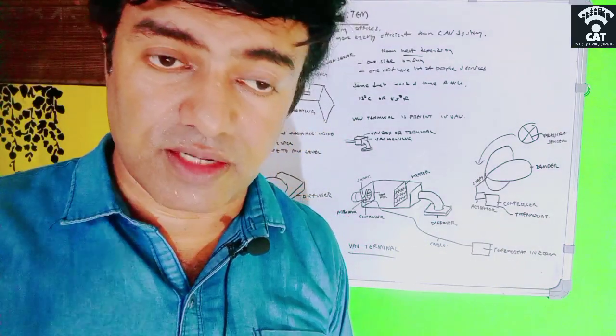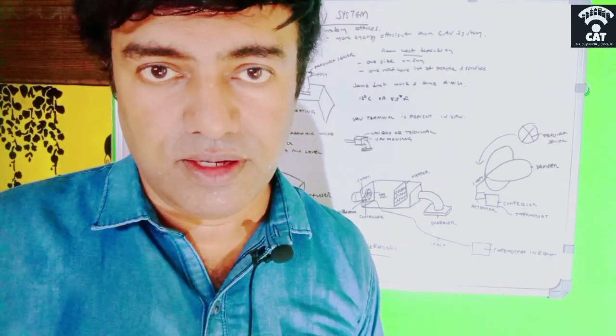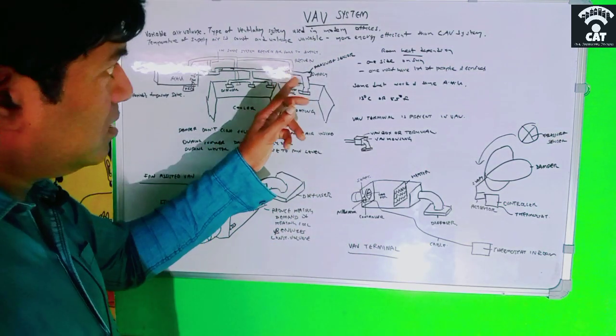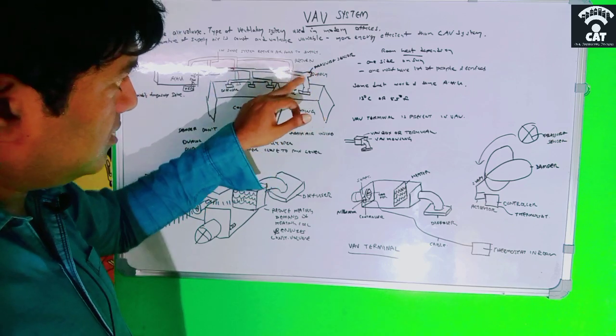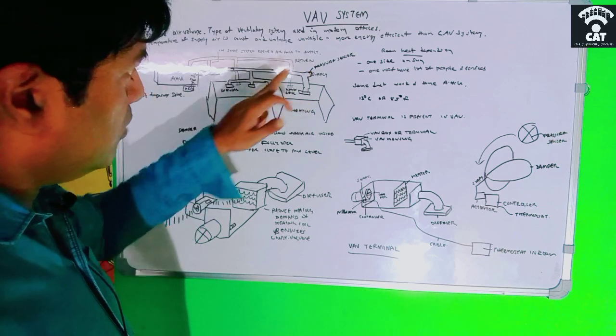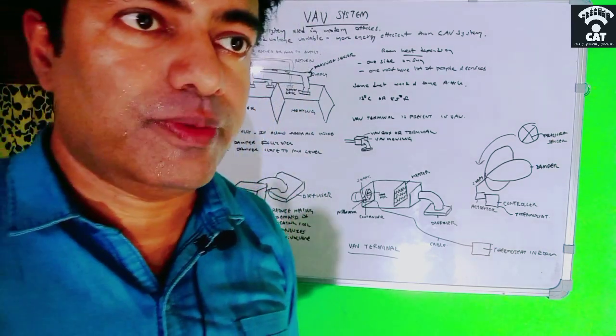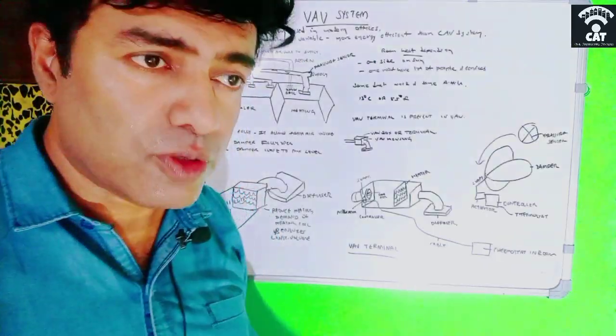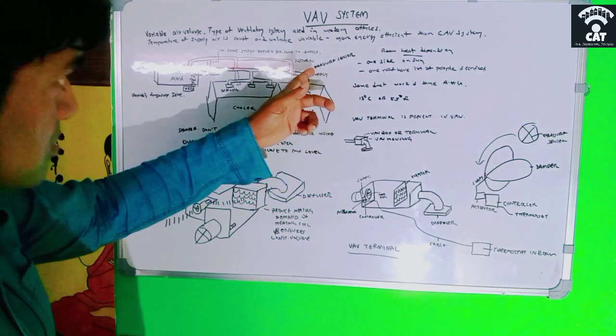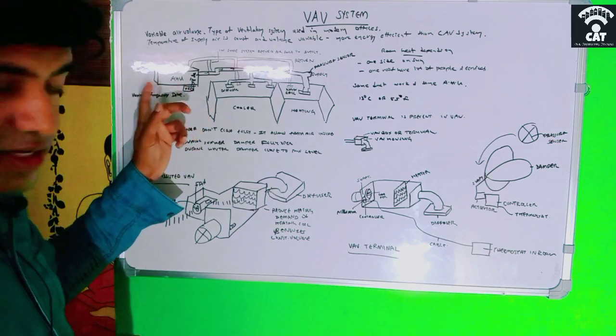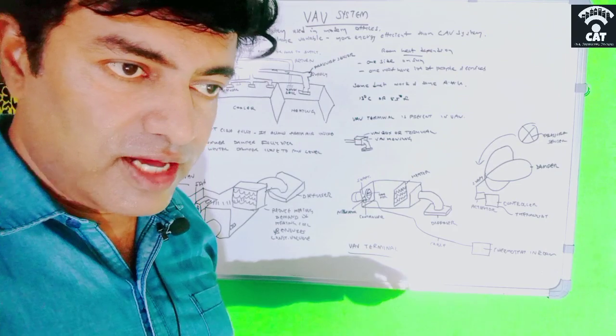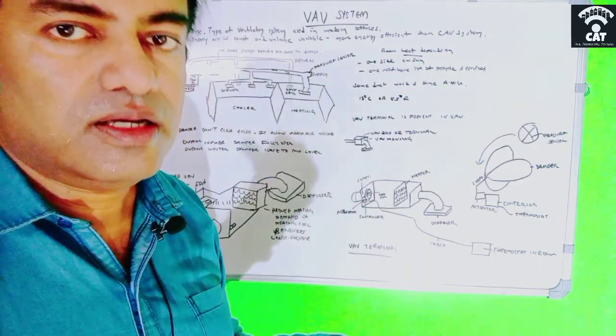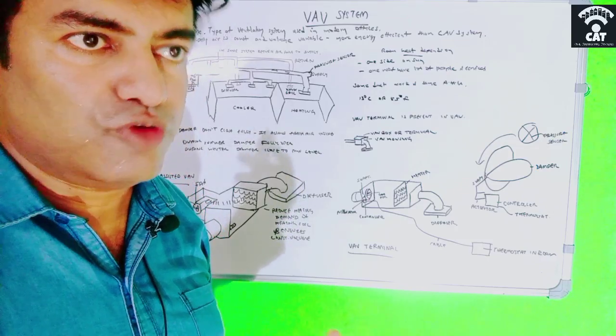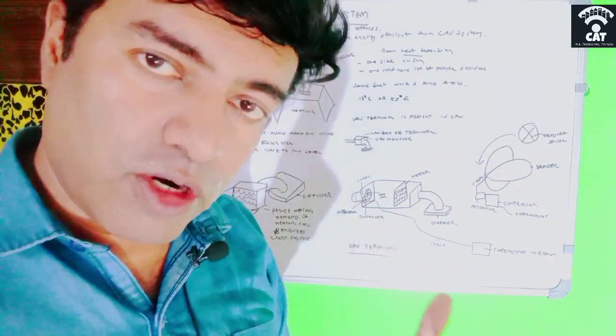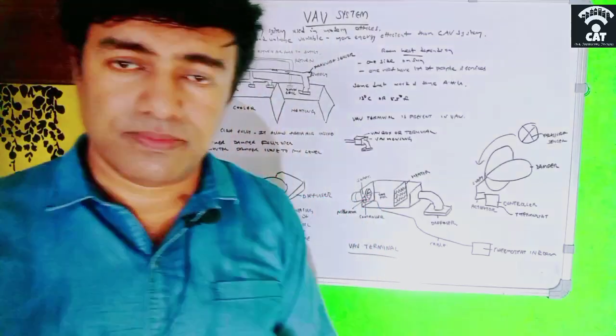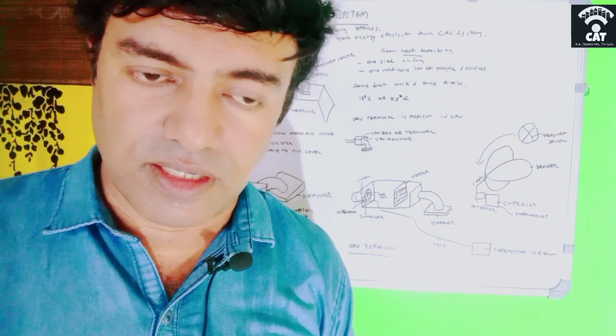If the pressure variance is there, then the diffuser will have less supply of air. So in order to avoid that, we place a pressure sensor at the end of the supply duct. You can see here, at the end of this supply system, there is a pressure sensor. It can detect the minimum standard pressure which should always be present in the supply duct. If it goes down, the pressure sensor will send a message to the variable frequency drive present in the AHU, the VFD. The VFD will then tell the fan to increase its running capacity or pressure. So the fan will increase the pressure and maintain the pressure inside the supply duct. These are the systems through which modern office ventilation works nowadays.